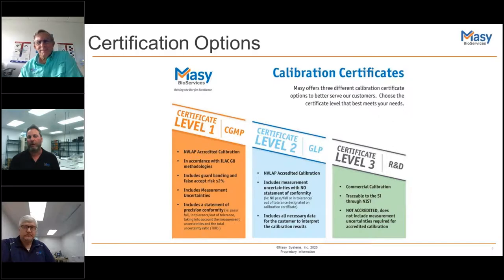So some of ours, we actually go with option two. They give us the data, they give us the uncertainty. We have a process in place at Masy where we receive that information, look at it, and put a cover sheet with an explanation - we looked at the uncertainty, did the calculations, and this is our number, which is a bit wider than the manufacturer's, and this is why we choose option two. So you might not have to have option one - option two gives you the ability to take the information and run it through your own criteria.